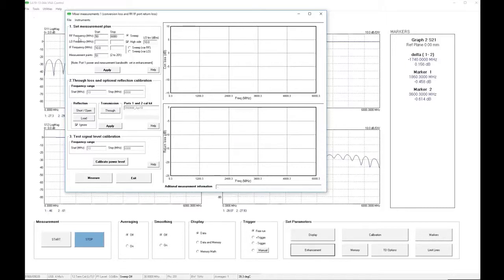We now go here to the top set of text boxes and radio buttons, and this is where we tell the software what measurement plan we want to use. So first of all, we have 3 radio buttons, and with these we can choose whether we're going to sweep the RF frequency or sweep the IF frequency. I've selected a sweep of the RF frequency and selected that we're going to sweep from 50 MHz to 3 GHz, which is just within the bandwidth of the mixer that we have here to test.